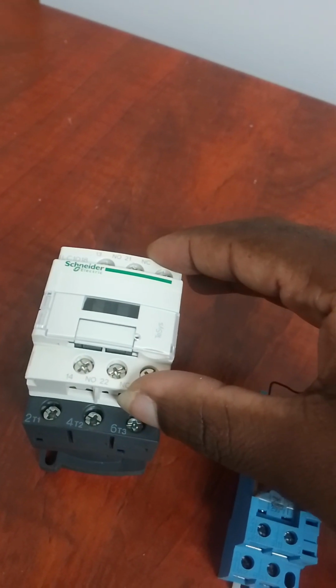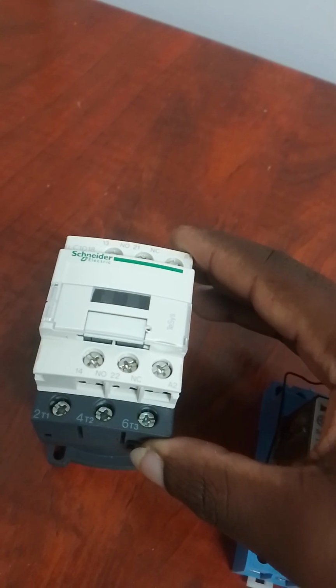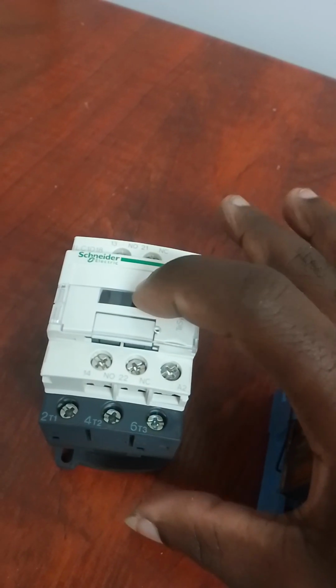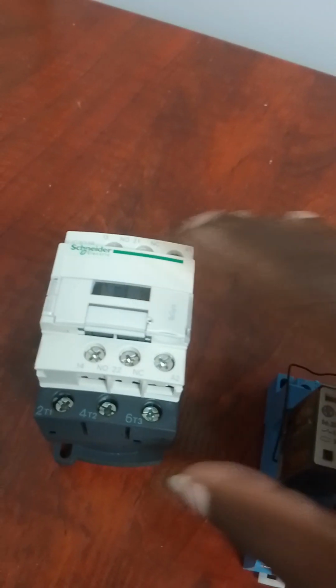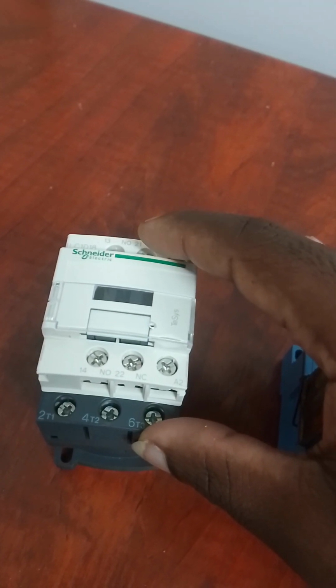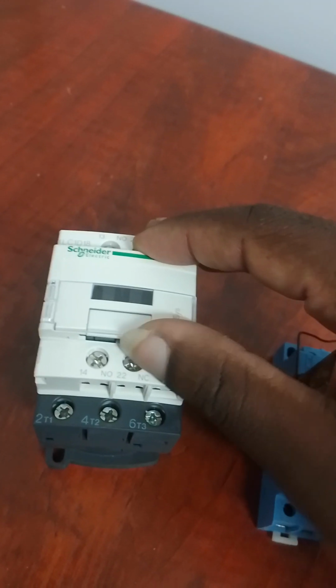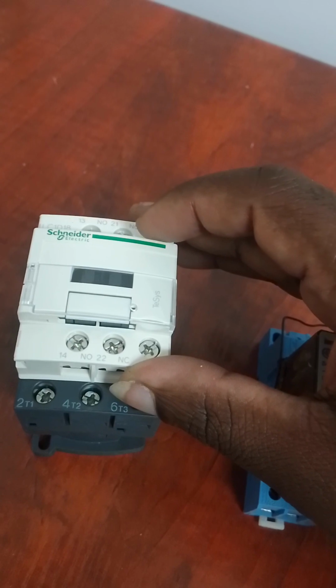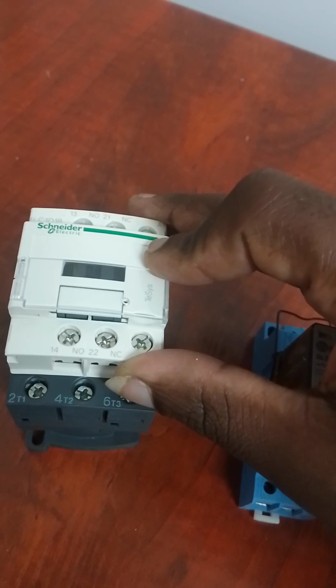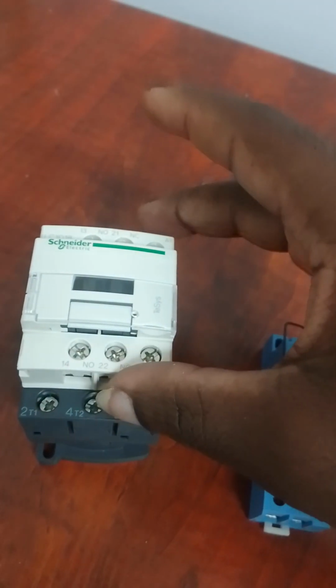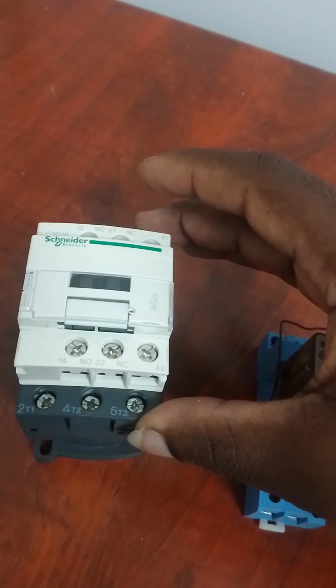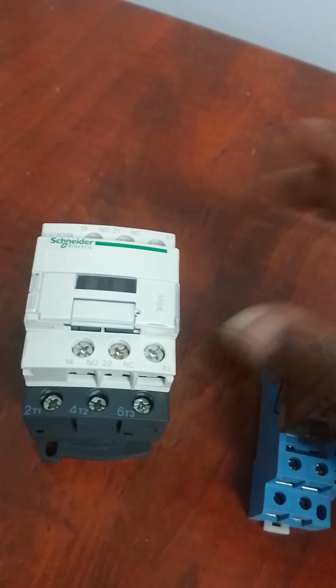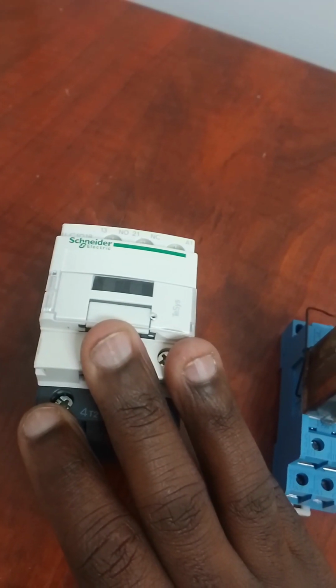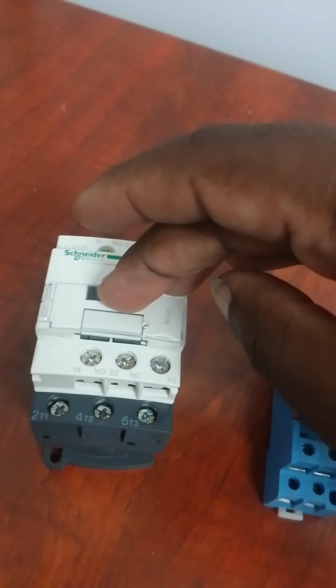There is this contactor and we also have another one, a power contactor, which is bigger than this one. You find this power contactor where there is a big motor, in what we call a motor control center. So you see a big contactor for protecting the motor, to make sure the motor is safe. When you find another big contactor, the smaller one controls the bigger one, and the bigger one controls the motor.